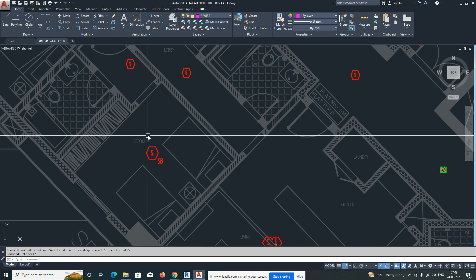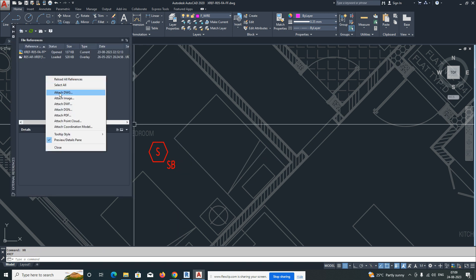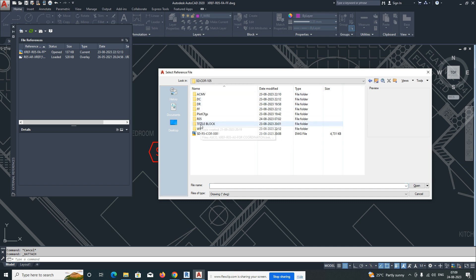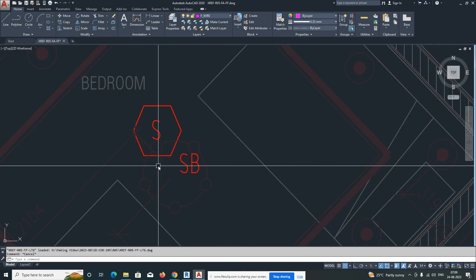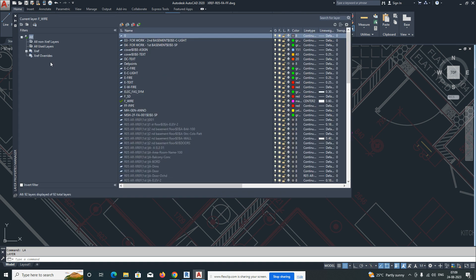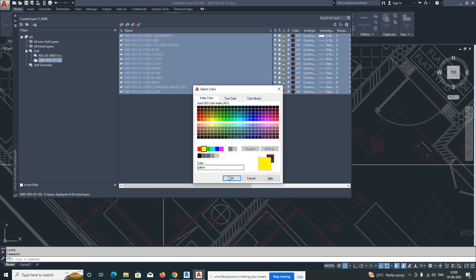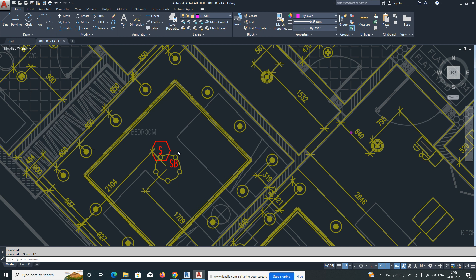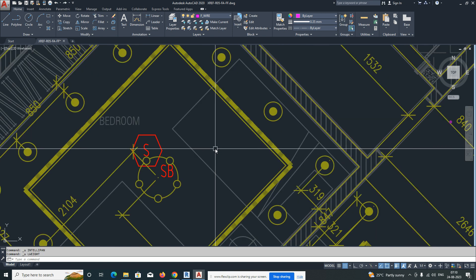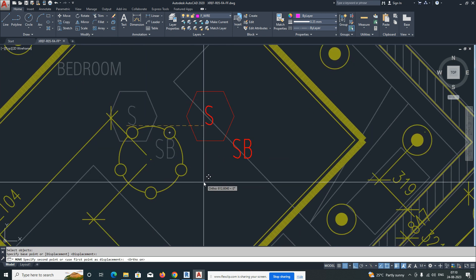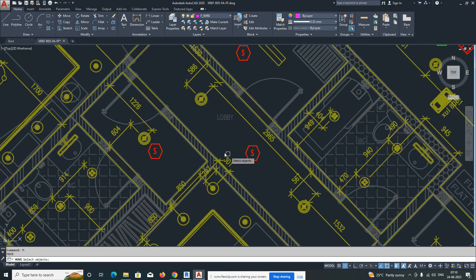The fire alarm location may be variable depending on the lighting drawing for the apartment. For example, using a lighting layout, we need to coordinate fire alarm placement with the lighting. I'm changing the color of the lights to yellow so you can see where all the lights are placed. We need to move the fire alarm system away from the lighting positions — that is ceiling coordination.